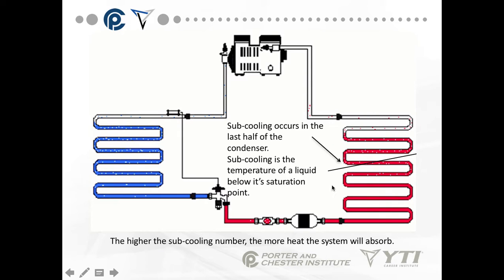Sub-cooling occurs in the last half of the condenser. We come in as a superheated vapor, condense from vapor to liquid, then further cool below what's considered its saturation point — the point where all the vapor becomes a liquid. The higher the sub-cooling number, the more heat the system will absorb.